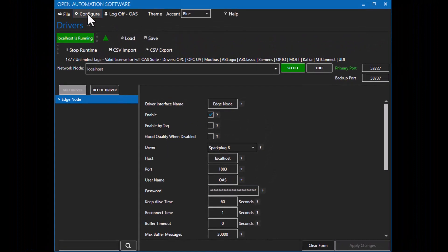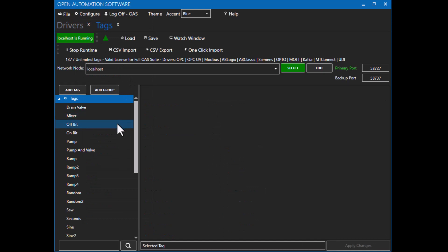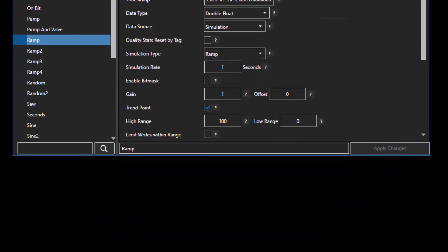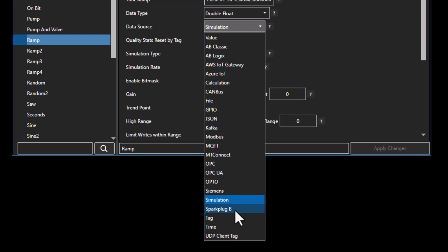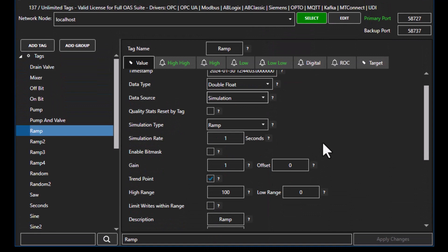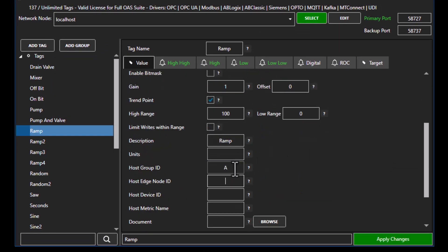We're complete with that driver interface step — we'll select Add Driver. Now we'll move to Configure Tags to set up the tags I want to publish. I have the default demo tags installed with OAS — I'll just use one of them here as a ramp signal. I can use any data source OAS supports, including Modbus, Allen Bradley, Siemens, or OPC UA. I'll put in the group ID of 'A', edge node 'E' — matching what we specified in the driver interface — the device ID as 'sim', and the metric name as 'ramp', then select Apply Changes. That tag is now ready to be published as a metric node.